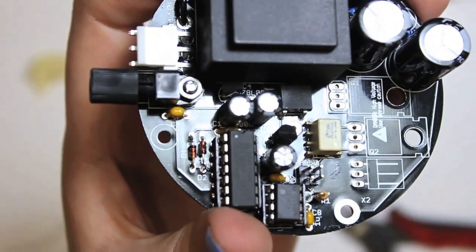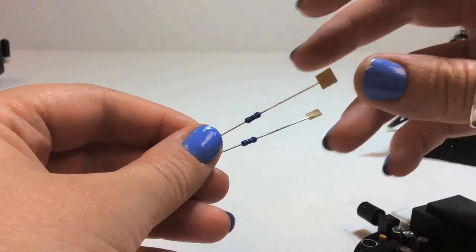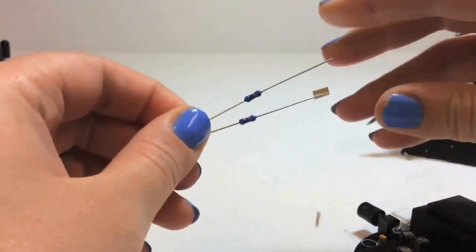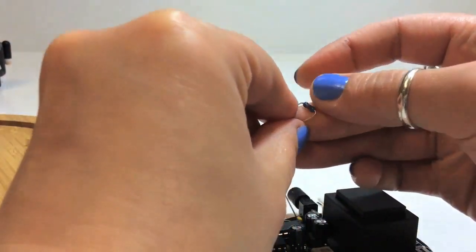In this video I will be showing you how to install the main board power components. First we install the R2 and R3 resistors. These are very important because without them the capacitors cannot drain their energy and the board will be unsafe to service.